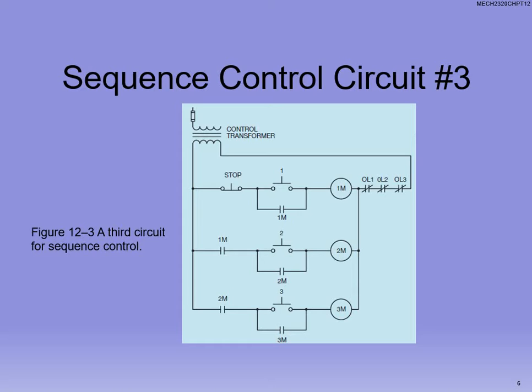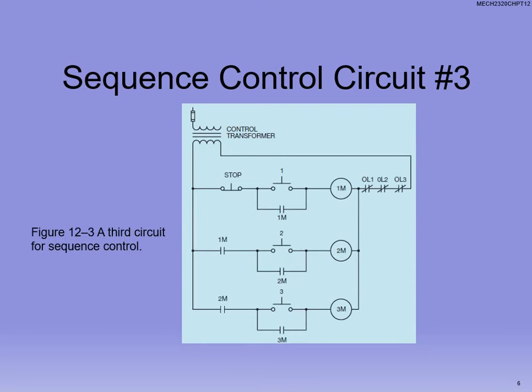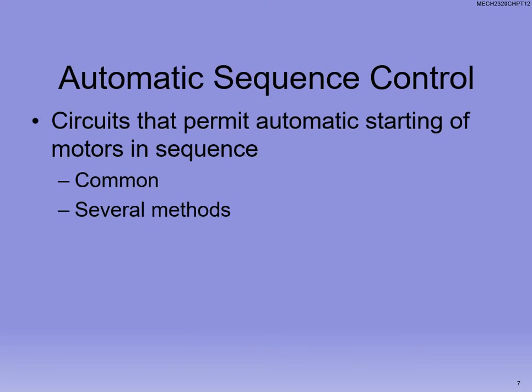The third method is almost identical to the previous method, only we've put the contactors for 1M and 2M before the push button instead of after. So in method 2, the 1M and 2M contactors are after the push buttons, and here they're before the push buttons — that's really the only difference. It still stops things because it's still in series, so it still works.